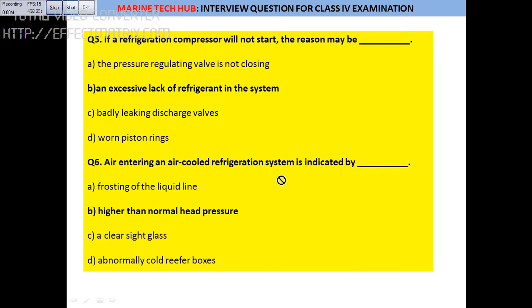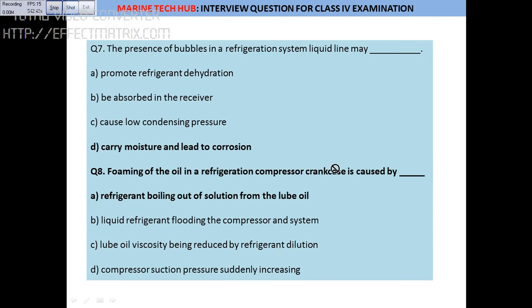Question 6: What happens if air enters a refrigerant system? Normally, whenever you are charging the system, you must first create a vacuum so that no air is present. If air is there and you charge without making a vacuum, you will get trouble and will not get a good refrigeration effect. In that case, the pressure head on the gauge will be higher than normal. The answer: whenever air is in the system, the pressure head will be more than normal.